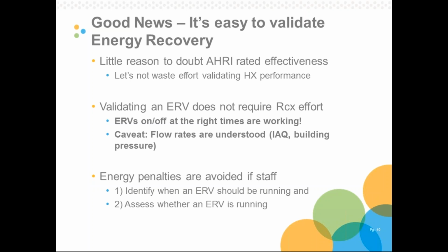So first of all, I'll just say there's no reason to doubt AHRI rated effectiveness. We need to, and maybe this is my impression of this, but we need to stop wasting effort trying to validate effectiveness. We don't care about the effectiveness of heating and cooling coils because we take it for granted. What we do when we implement heating and cooling systems is make sure those coils are installed and designed as part of a broader system that performs a goal. And that's really what energy recovery is about. It's not about a specific heat exchanger we're putting in an air handler. It's about all the sequences and sensors and installations that we use to make energy recovery happen.